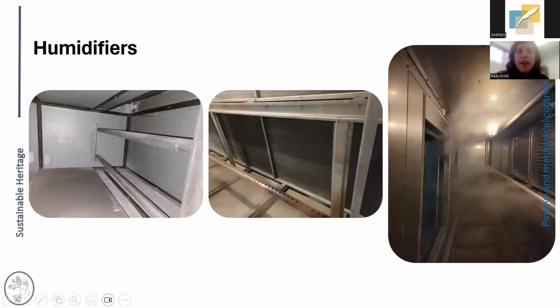Okay. The reverse of the dehumidification component is humidification. I just wanted to show you some images of what humidifiers would look like within the system. On the far left, you can see this piping going across. In the middle image, you can see the holes in the top where the water is injected into the air. On the right, you can see an image of it in action with that steam being added directly into the airstream. So by literally adding water to the air, that's how we're increasing the amount of moisture within that bucket. That's how we're humidifying.